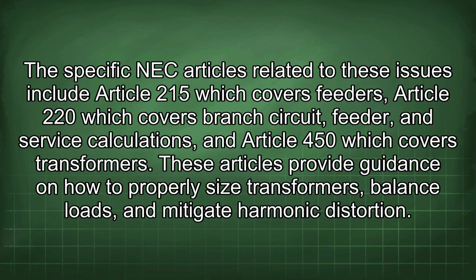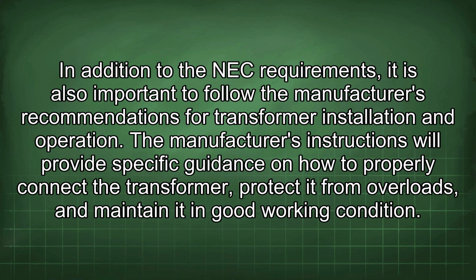The specific NEC articles related to these issues include Article 215, which covers feeders, Article 220, which covers branch circuit, feeder, and service calculations, and Article 450, which covers transformers. These articles provide guidance on how to properly size transformers, balance loads, and mitigate harmonic distortion. In addition to the NEC requirements, it is also important to follow the manufacturer's recommendations for transformer installation and operation. The manufacturer's instructions will provide specific guidance on how to properly connect the transformer, protect it from overloads, and maintain it in good working condition.